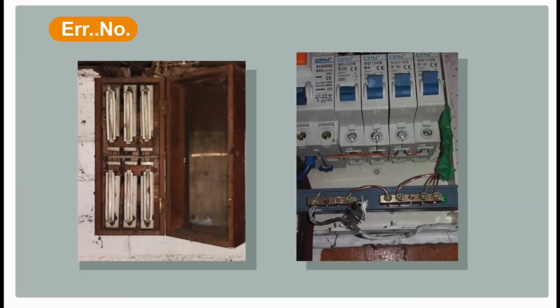So yeah, sometimes boards can just be too old. Look at this one here, you don't want to be using that. This is actually still live and in use, but no, you don't want to be using that as your temporary supply, that's done its time. But just because it's old doesn't mean it's bad, and just because it's new doesn't mean it's good. I mean, look at the state of this. This is quite a new thing. You don't want to be using something like that either. So even if it's a newish supply, newish board, you still got to check it's all good and suitable.